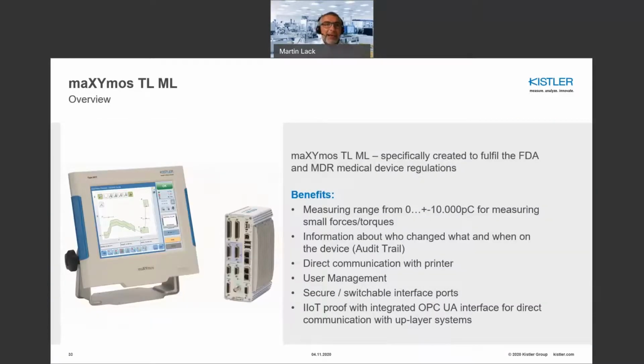In a nutshell, the maXYmos TL-ML is created to fulfill the FDA and MDR medical device regulations. In the TL-ML we also have a low-range measuring possibility, so we can measure low forces and torques. We have audit trail functionality - who changed what and when - direct communication with the printer, and user management, so you know exactly who changed parameters on the device. We also have IoT readiness with integrated OPC UA for future communication with the upper layer system.